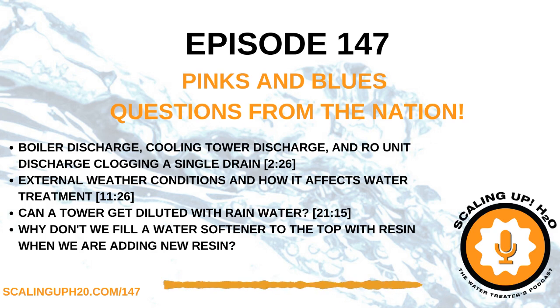Now, when a tank goes into regeneration, if you only have one, any water the system is calling for is going to get bypassed from that water softener, and you now have hard water going into that system. You have calcium and magnesium going into the system. If you have a twin system, whenever one system gets backwashed, the other system goes online, and now you're never putting hard water into the system. And folks, if you have a boiler, single systems are meant for houses. Single systems are made for laundries where they want to make the lather easier to occur with soaps. That's not the boiler system. The boiler system, we cannot have any hardness going into it, so it always, always, always needs a twin system in there.